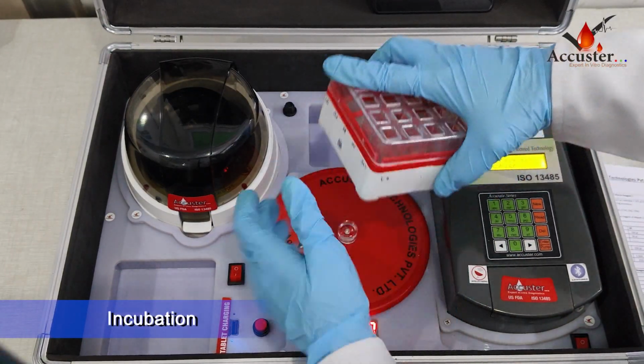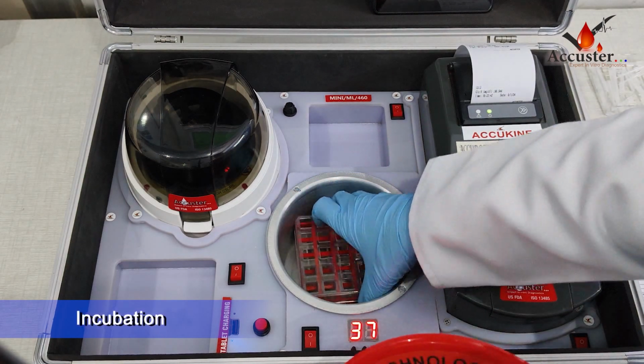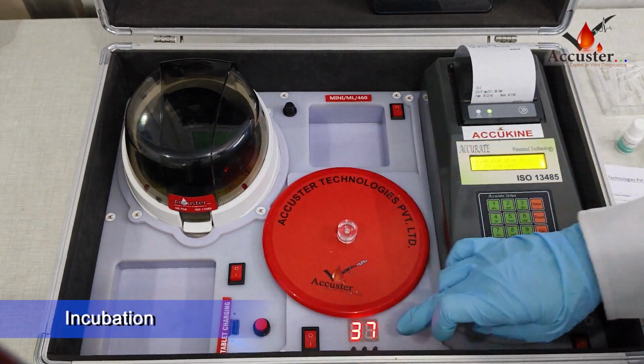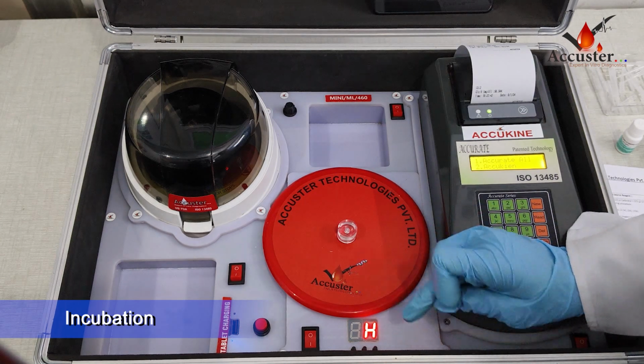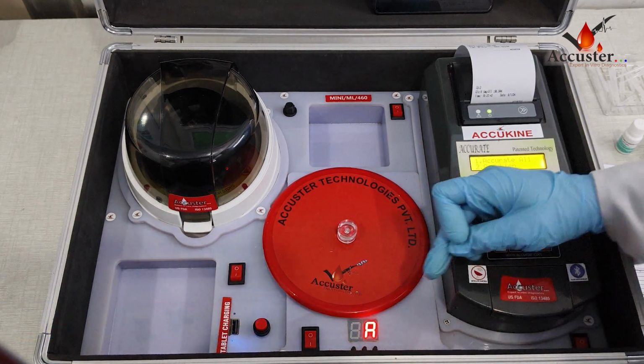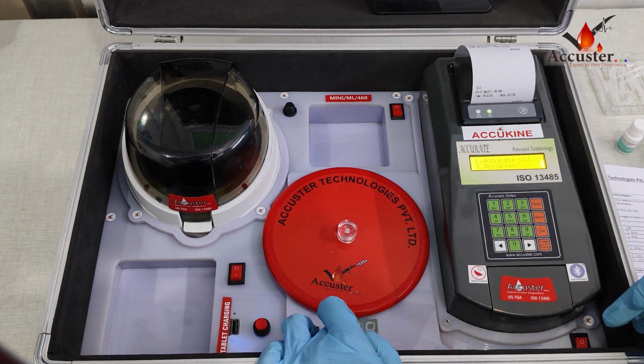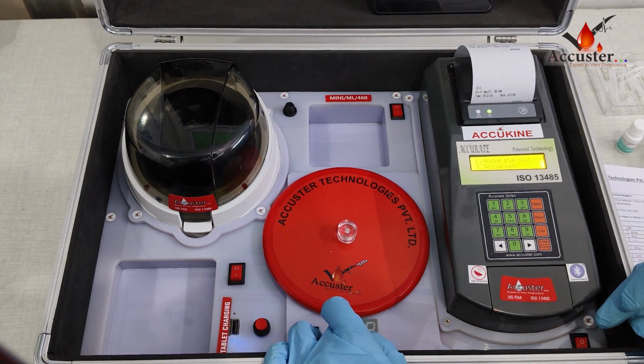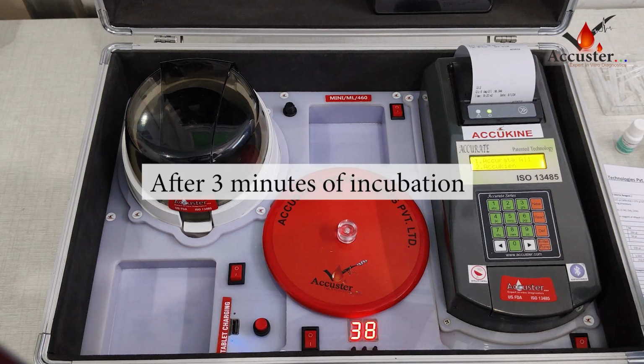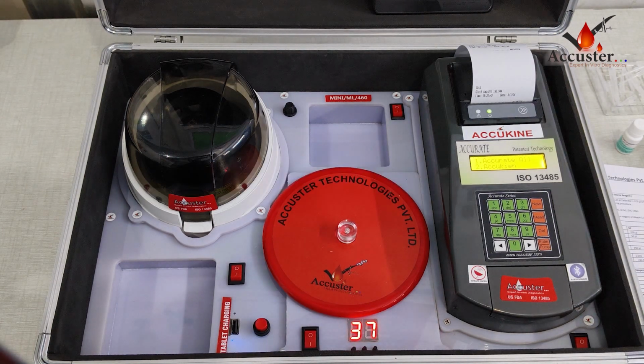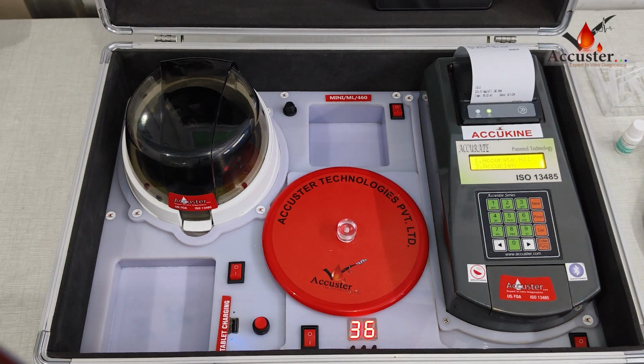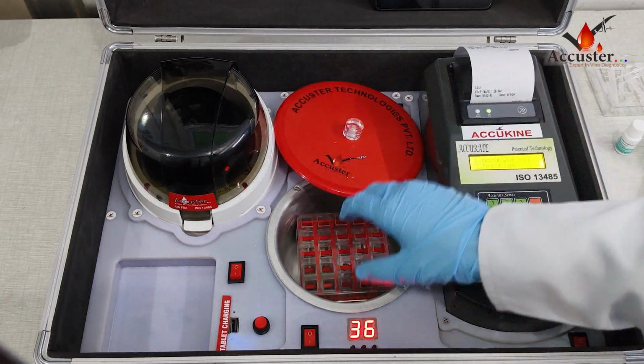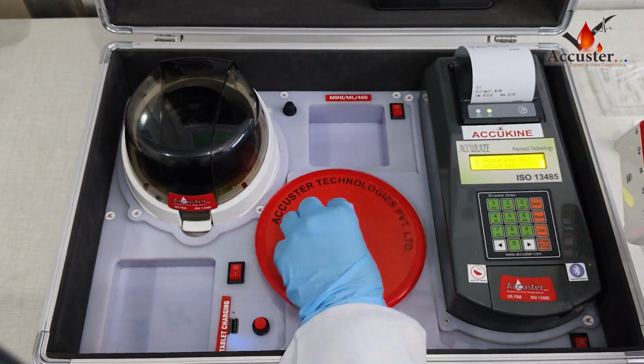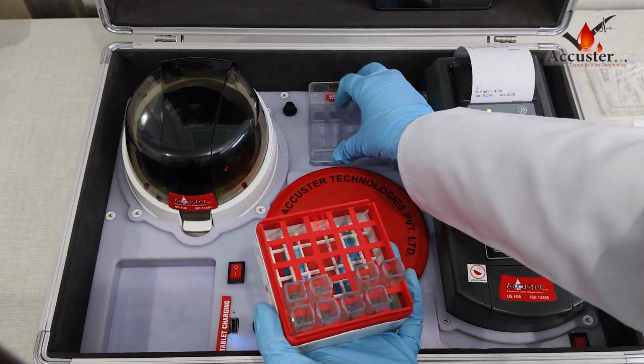Now we'll begin with the incubation process. Calibration control and sample are now ready for incubation. We will incubate these for 3 minutes at 37 degrees Celsius temperature, and we'll set a timer for 3 minutes. Now 3 minutes are passed and the incubator started beeping. It means incubation is completed. After incubation, we will take out the cuvette containing calibration and quality control from the incubator.